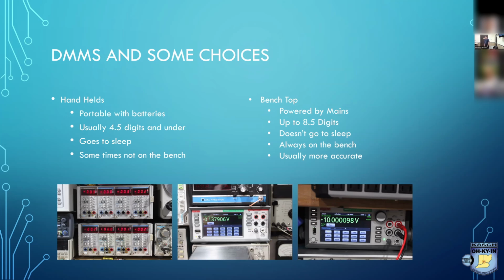With the mains powered meters, they don't go to sleep and they'll stay on as long as you leave them on. That's actually really important at some of the higher accuracies. Some of the warm-up times are 1.5 to 3 days, depending on what the device is.